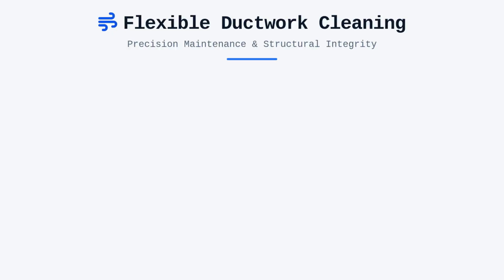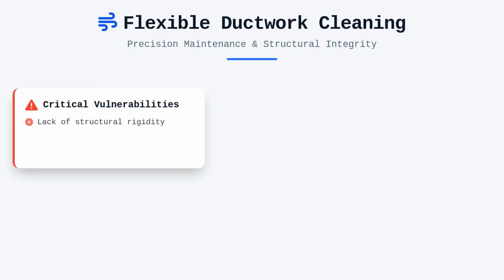Flexible ductwork poses a unique set of constraints that require a delicate hand when performing cleaning operations. While these ducts are excellent for navigating around building obstacles, they lack the structural rigidity of metal and are easily prone to kinking or tearing. If you apply excessive mechanical agitation or use brushes meant for rigid sheet metal, you risk puncturing the inner liner or causing the wire helix to collapse. This damage can permanently increase resistance in the system and lead to premature failure of the flexible duct itself.